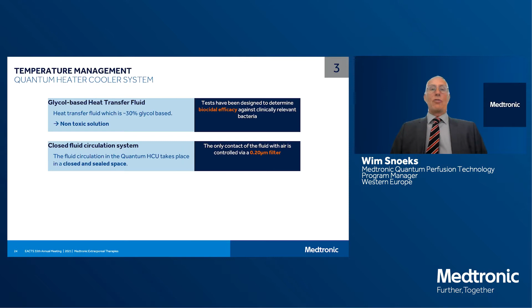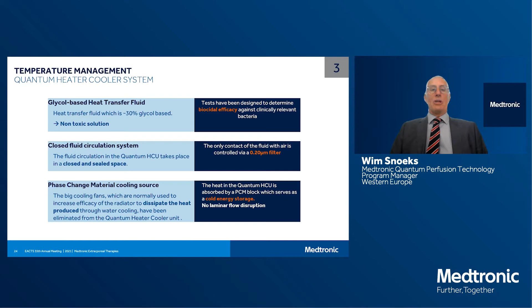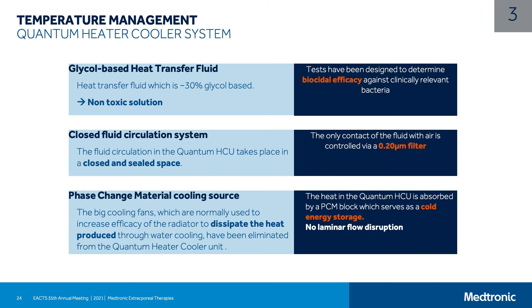The phase change material is the cooling source. Big cooling fans, which are normally found in traditional heater cooler systems and used to produce deep water cooling, have been eliminated from the system. So the heat in the quantum heater cooler units is absorbed by the phase change material block, which serves as the cold energy storage. So there is no laminar flow disruption.